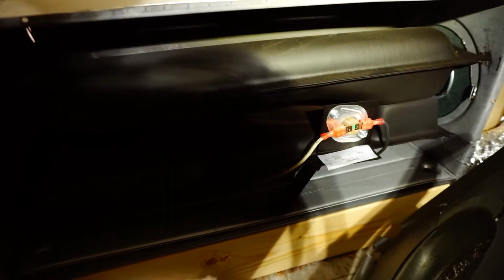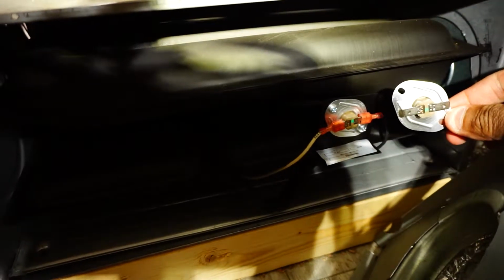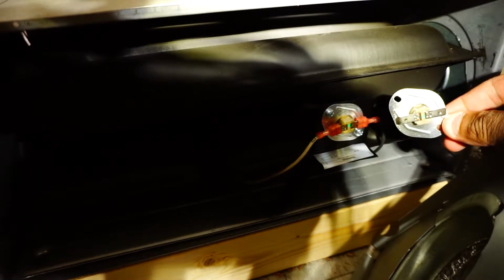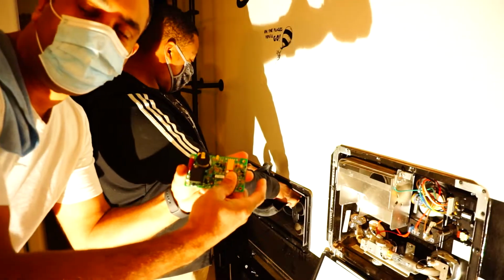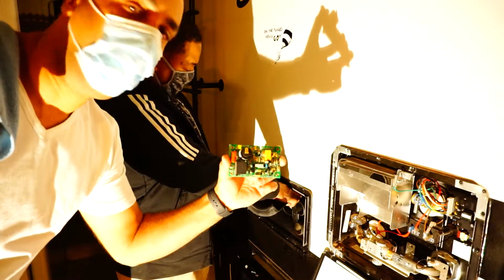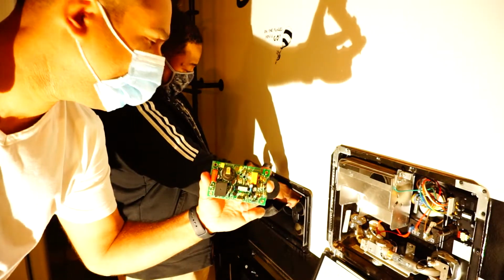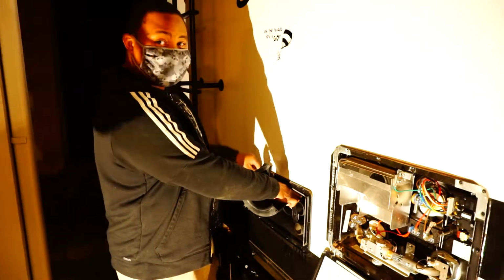The next reason is a faulty high limit switch, whether it's too sensitive or faulty for whatever other reason. It's a relatively cheap part, about $10. So a lot of technicians check the airflow and then replace the high limit switch. The third thing could be an electrical board that is not working properly, and that's also one of the parts that a lot of technicians like to replace without spending a whole lot of time on troubleshooting.